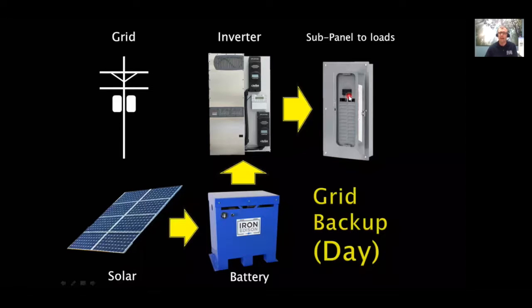When that pump comes on, maybe it has to come on at night. In that scenario, I can program my inverter to recognize there's a very heavy load. I program a threshold, and if the load passes above it, the inverter can automatically ask for support from either the grid or a generator, or both, to support that load until we pass below the threshold and the pump has been turned off. This preserves what's left in my battery.